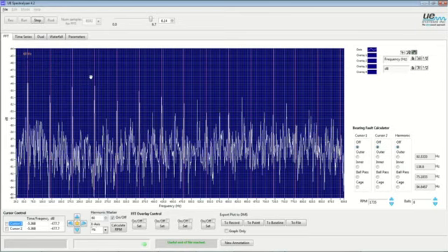There's a tremendous amount of 60 hertz spikes or peaks through the entire recording. Nearly every 60 hertz harmonic has a peak, and we have a lot of frequency noise, a rich abundance here telling me, yes, it's electrical in nature. So that's common for a purely corona event that's non-destructive. We have all the 60 hertz peaks and a lot of frequency noise.